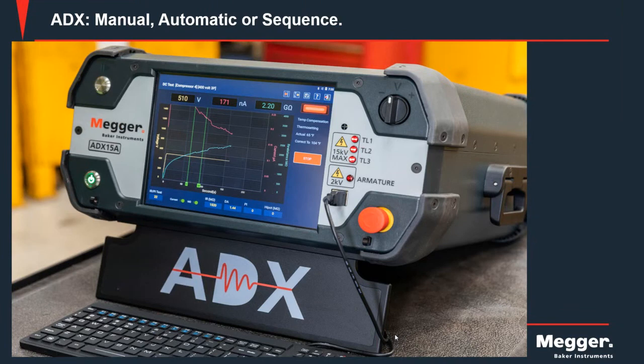Now, the sequence test is automated, and the sequence part of it means that we can run through maybe 7 or 8 different tests without actually starting and stopping the instrument. So as we, let's say, do a resistance test, and then we run through to an insulation resistance test, maybe a high pot, a surge test, a PD test, and so on. All of these can be set up in a sequence.